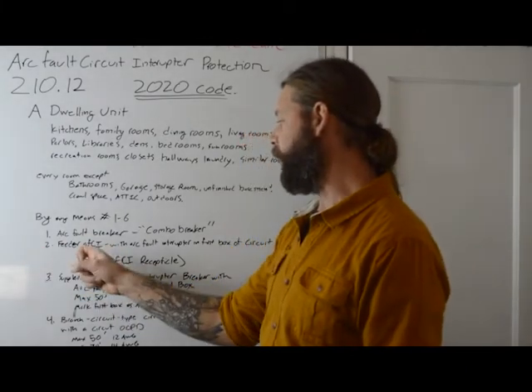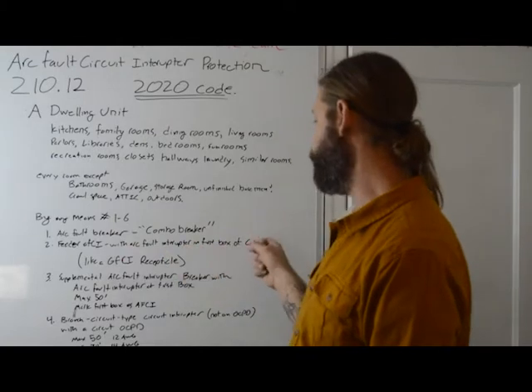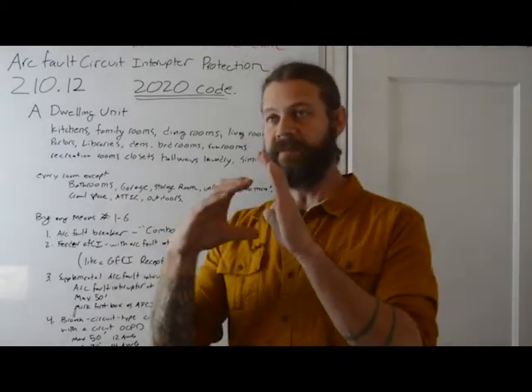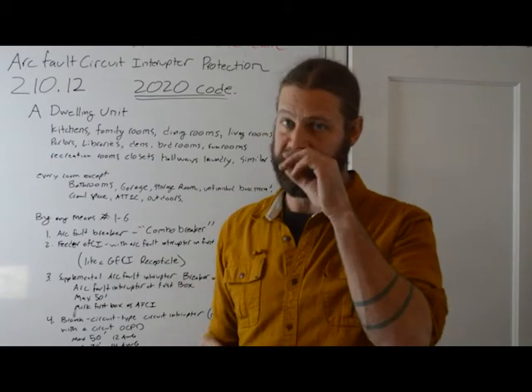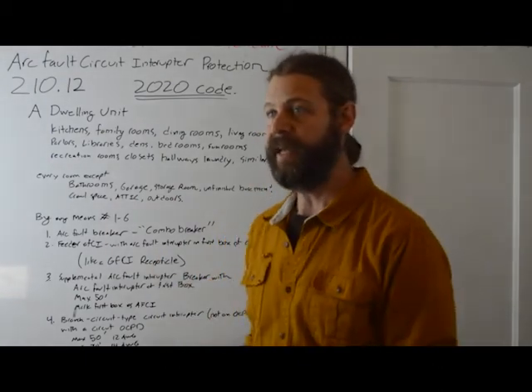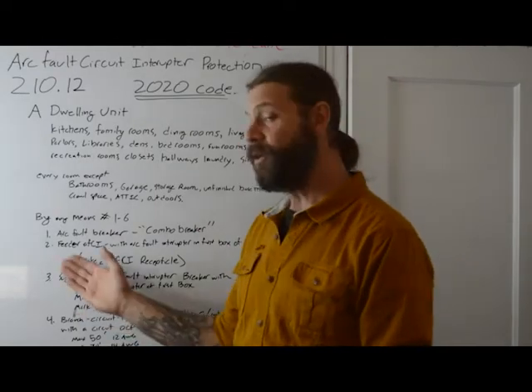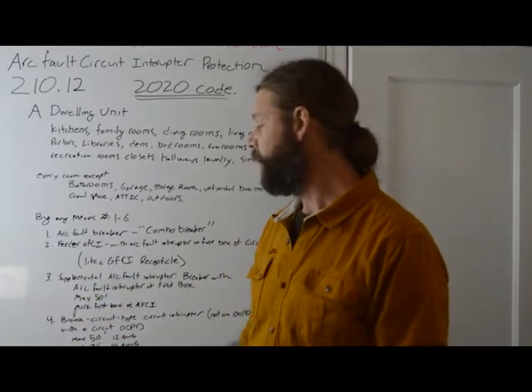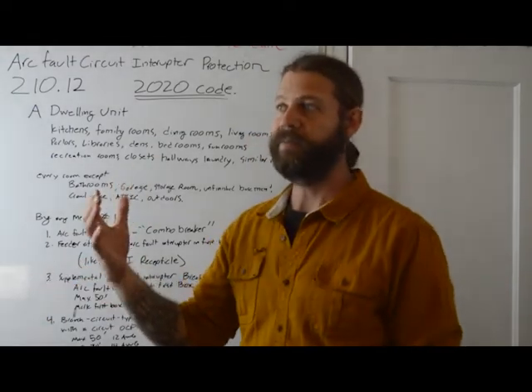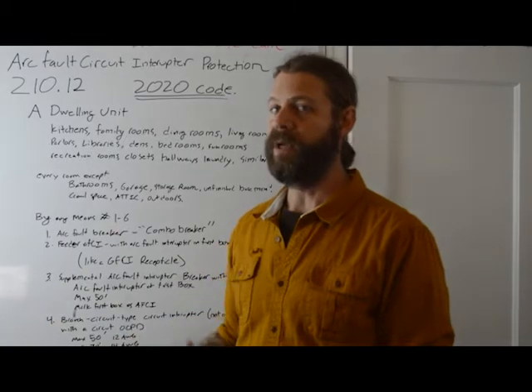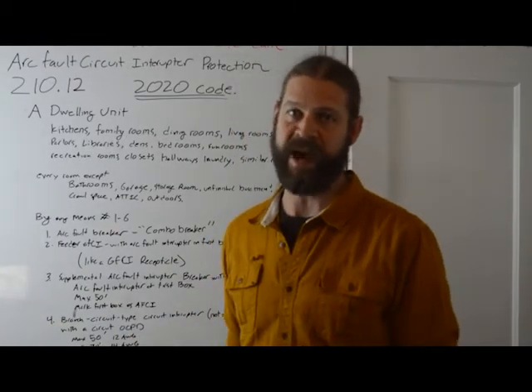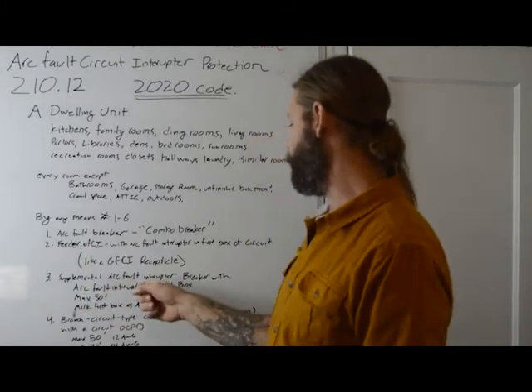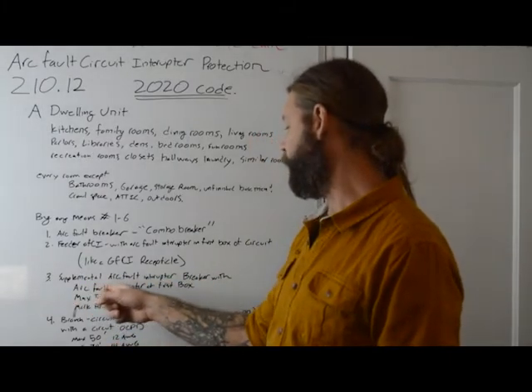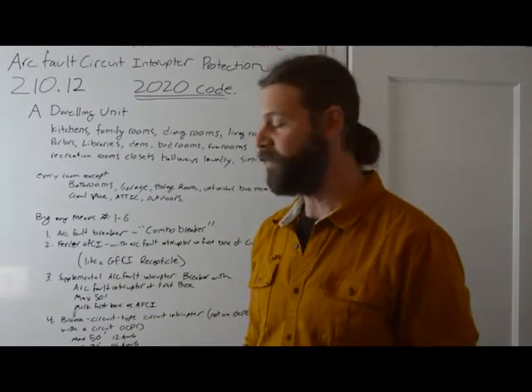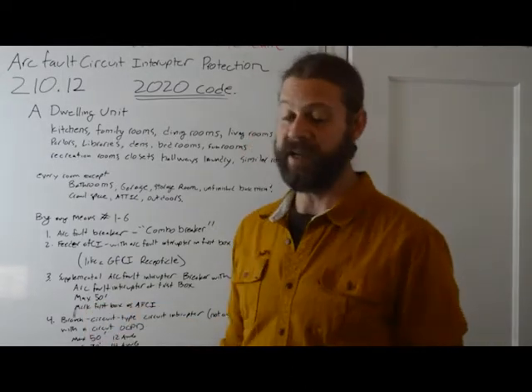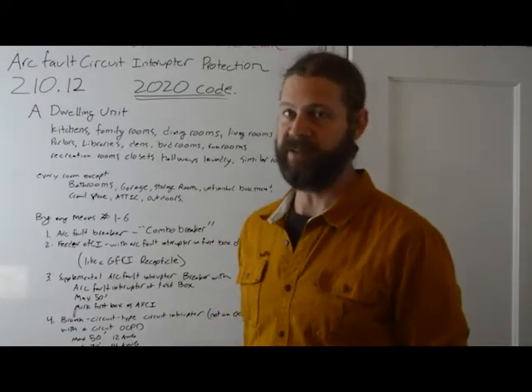You can also use a feeder type arc fault circuit interrupter with an arc fault interrupter in the first box of the circuit. Okay, it looks like a GFCI receptacle, but it's actually an arc fault circuit interrupter. So that combination is acceptable. It also goes 3, 4, 5, and 6, which are, I think, so obscure as to not particularly matter. They are supplemental arc fault interrupter protection that has an arc fault interrupter at the first box with a maximum of 50 feet, and you have to mark the first box as AFCI. I've never seen it. I don't expect to ever see it.